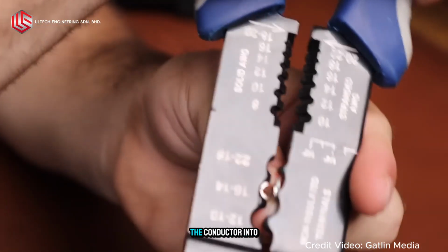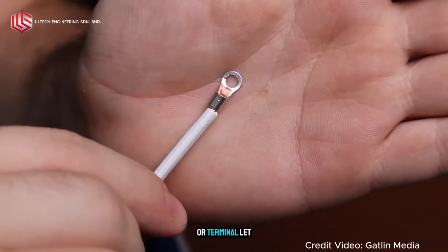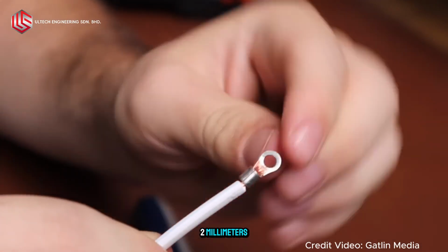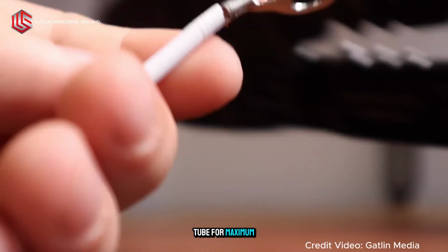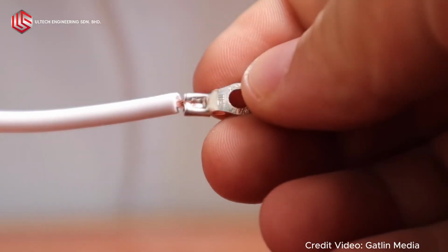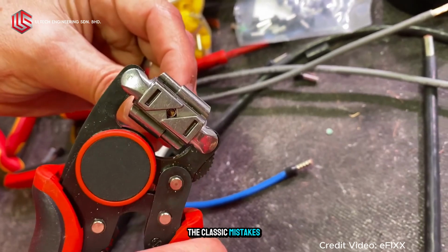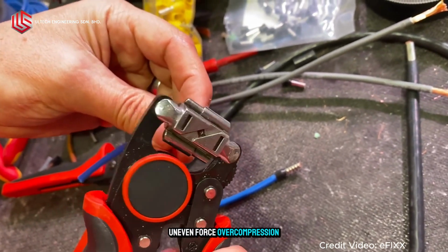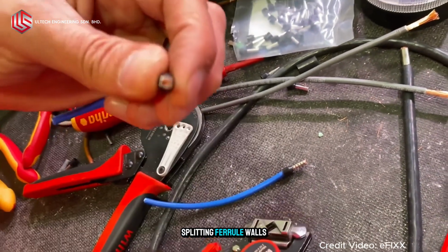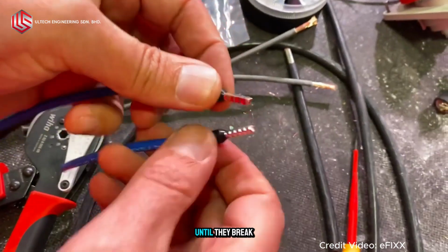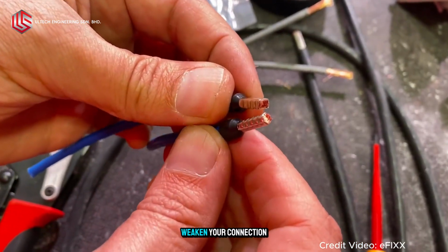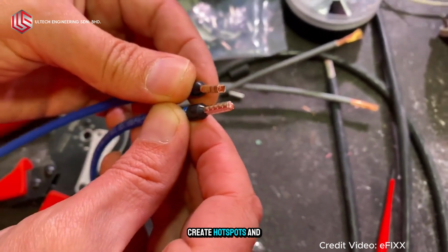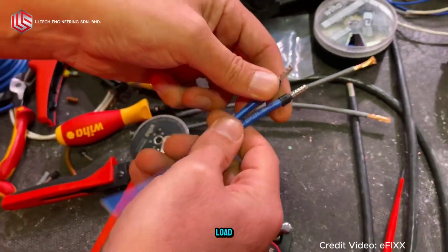When inserting the conductor into a ferrule or terminal, let it peek out just 1 to 2 millimeters beyond the copper tube for maximum electrical contact. But beware of classic mistakes: uneven force, overcompression, splitting ferrule walls, or crushing strands until they break. These flaws can weaken your connection, create hot spots, and cause failures under load.